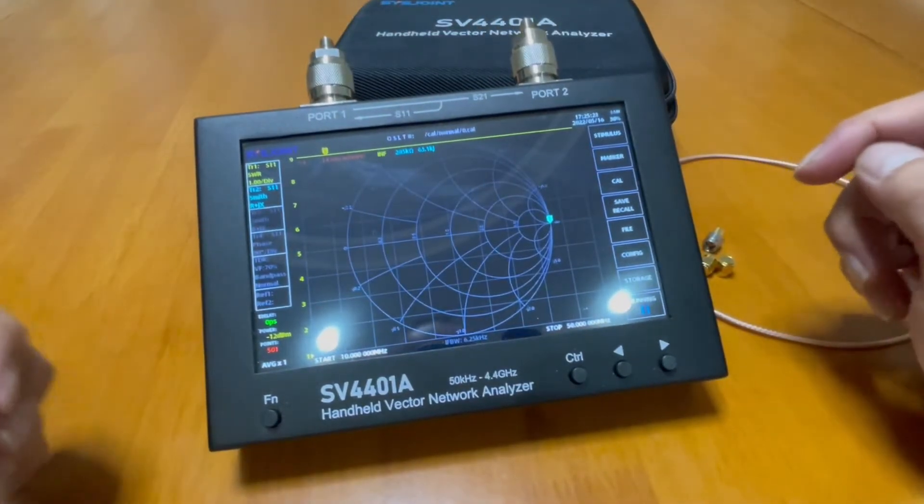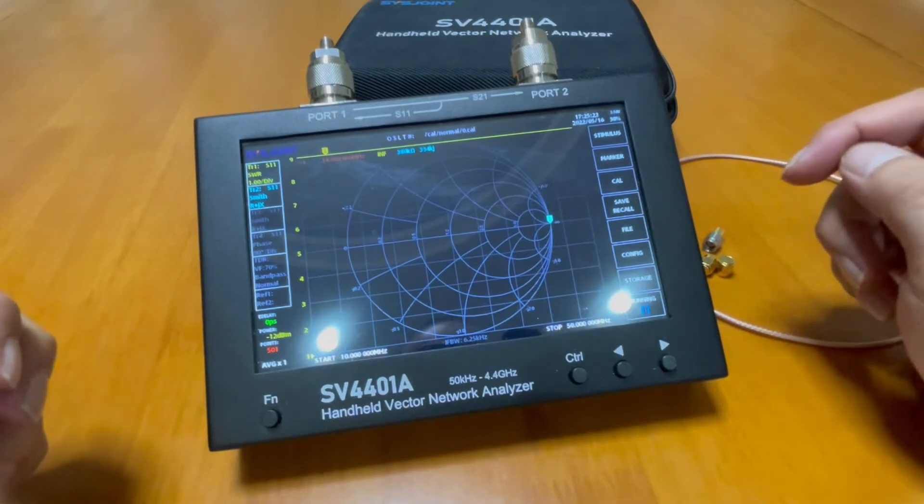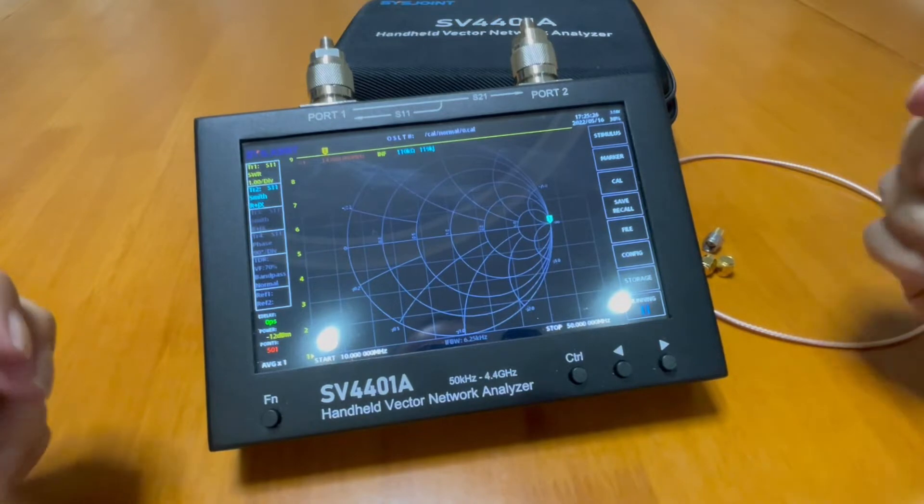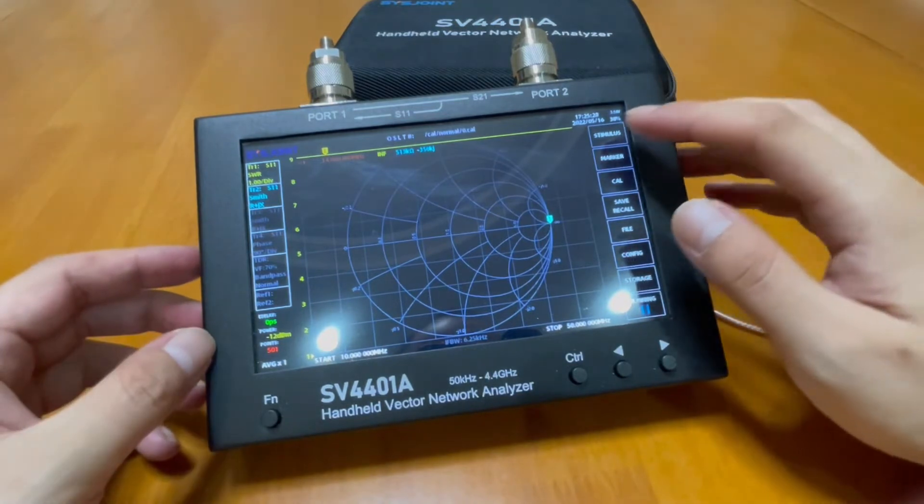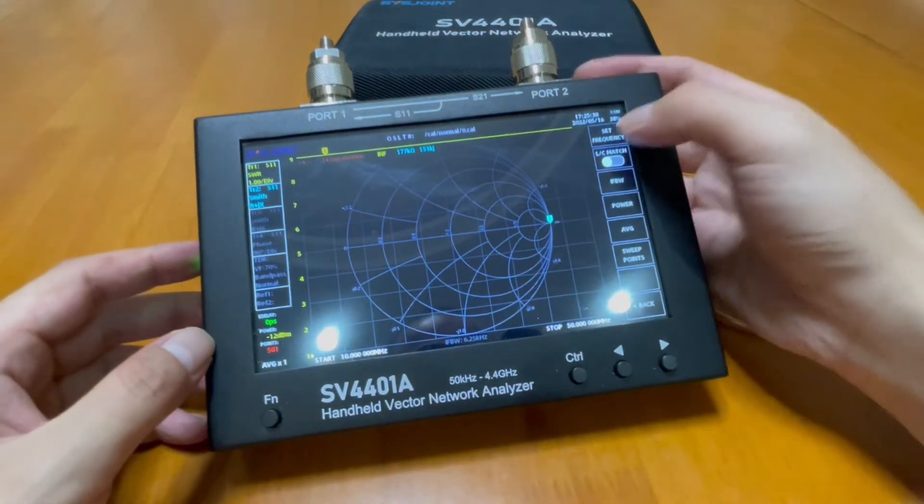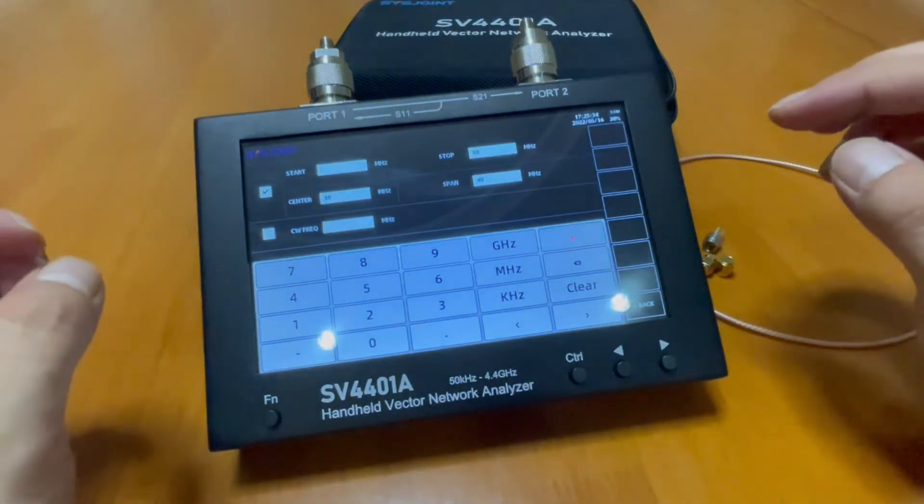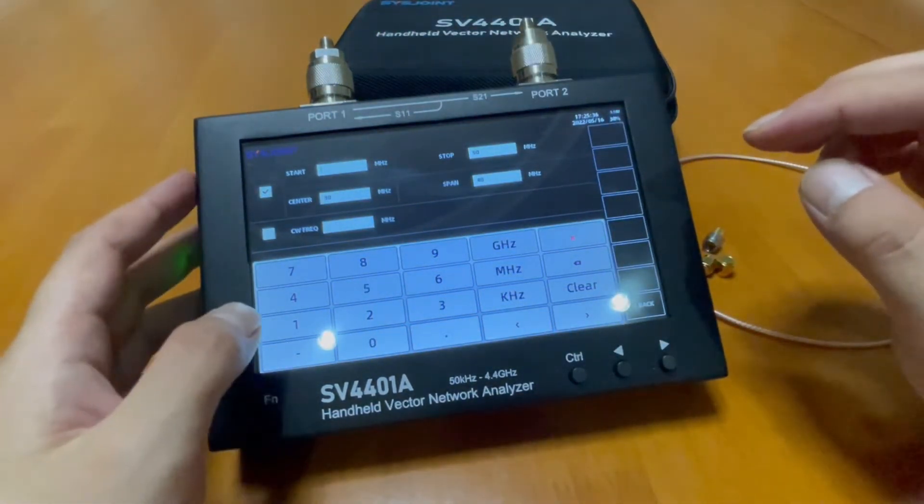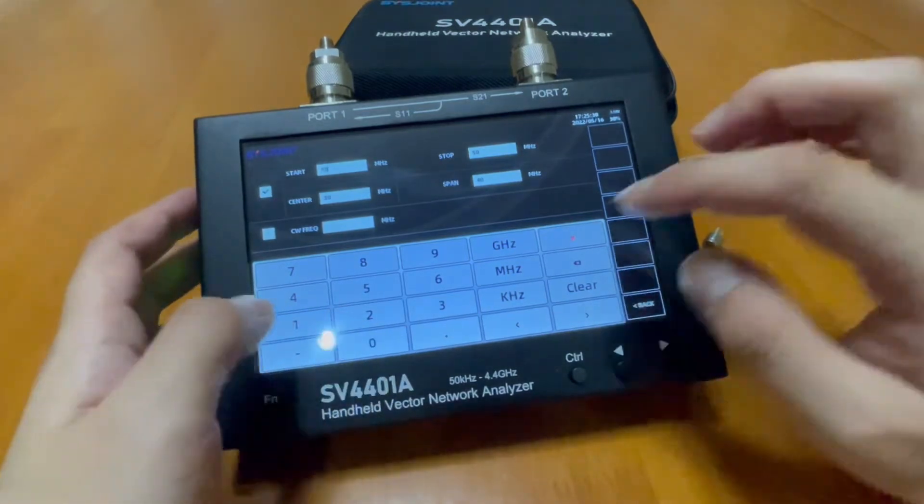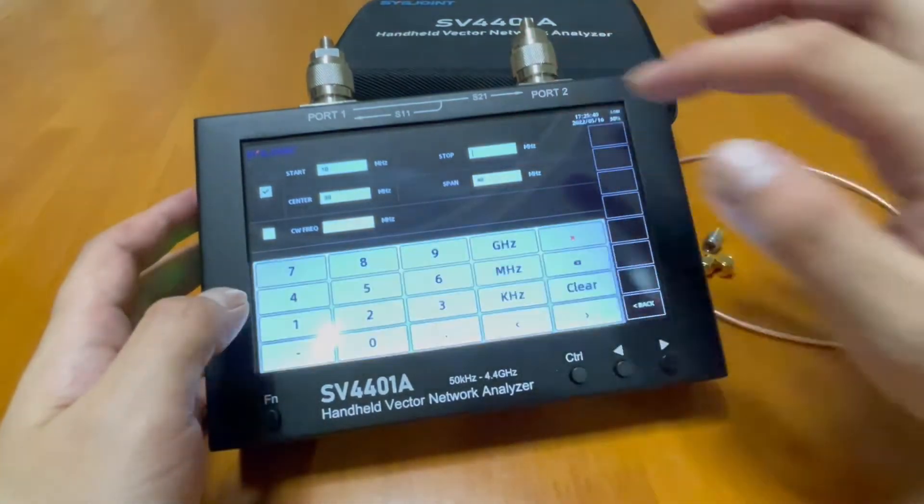After it turned on, what you want to do is always set the frequency range you're going to operate on, and what you're going to calibrate is also on the frequency range. We click on stimulus and set frequency. Let's say I want to calibrate on and operate on the frequency range from 10 megahertz to 50 megahertz.